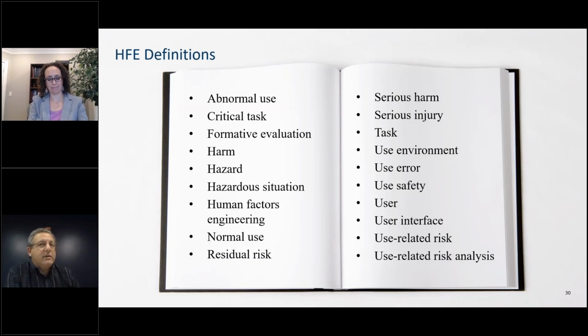The guidance now defines terminology critical to understanding use-related risk management. So definitions such as harm have been added, and this, along with hazard and hazardous situation, are now aligned with the definitions in ISO 14971, the international standard for applying risk management to medical devices. In that respect, we should note that damage to property or the environment is part of the definition of harm. So it's important for manufacturers to realize this, and it's something to consider during their use-related risk analysis.